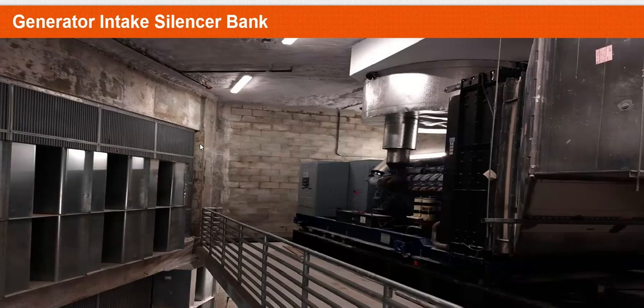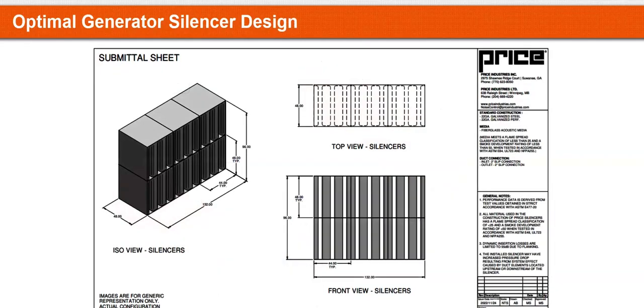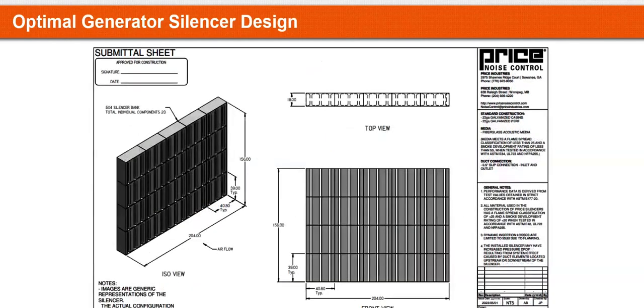We use the, obviously tested data, CFD analysis to really see the impact of these silencers on the system. But as they are installing them, you could see that the opening is fairly large relative to even the size of the generator itself. So this is the level of detail you would get working with a reputable manufacturer. This is the radiator exhaust, and as you could see right there, you're using a quarter of an inch of back pressure from a total of a half an inch that that generator can overcome. That is why at the inlet you have to have such a large opening so that you could reduce your pressure drop.